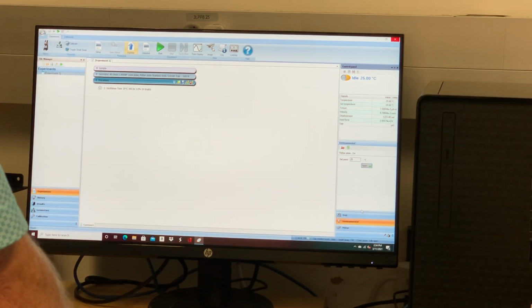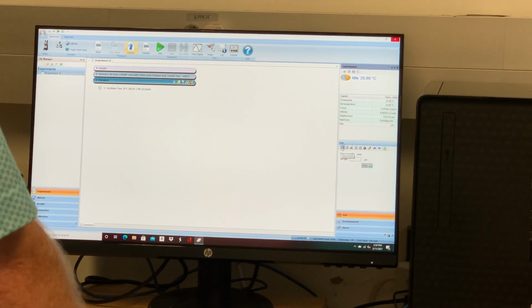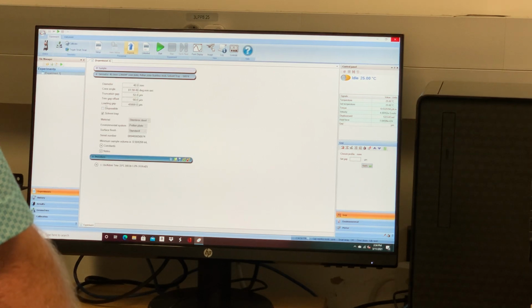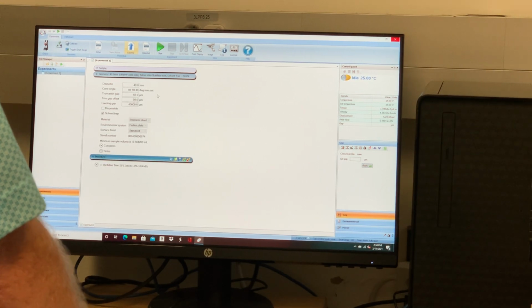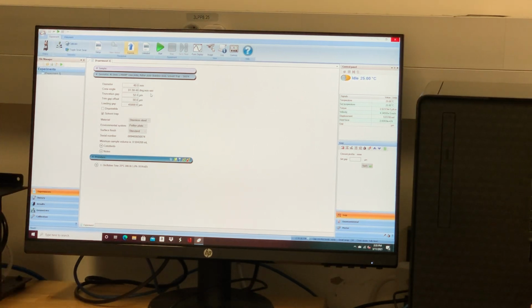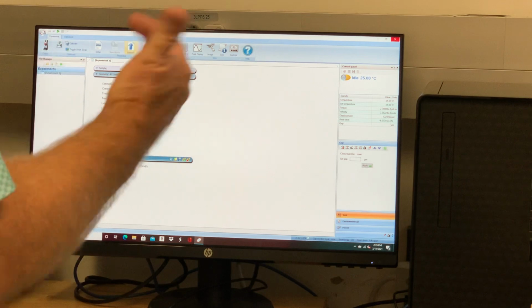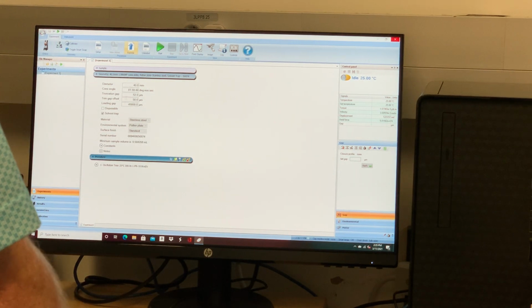If we go to our gap controls, over here we have stop the head, so for moving up and down. Go to geometry gap. So the geometry gap for a cone is the truncation gap, which is 52 microns. So for a cone, you have to run it at the truncation gap, okay? I'll go over the plate when we run another sample. So if we hit this guy here, it's going to go to 52 microns. We have trim gap, which I will go over when we run the other sample.